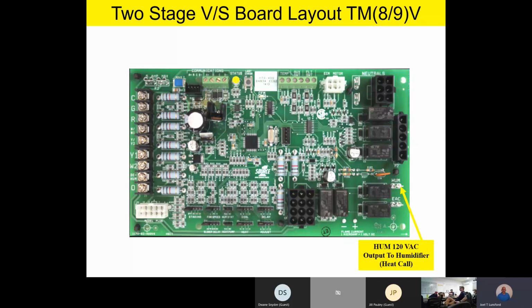This is one of the things I like about our controls quite a bit, is the fact that we give you a lot of these accessories already built in on the board. So in this example, that HUM terminal is going to be an output that's energized anytime you get a heating call, if you want to power up a humidifier during your heating call. You'll notice right to the left of it, there's a little black relay box right there. Let me move my cursor around a little bit. So right here, this little relay is actually an isolated relay for that humidifier output, which is kind of neat because now you're not pulling 24 volts over here off the terminal strip. You actually have an isolated 120 volt output right there on the board for a humidifier.